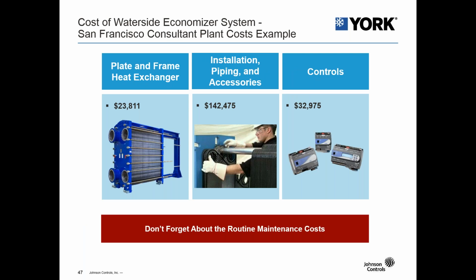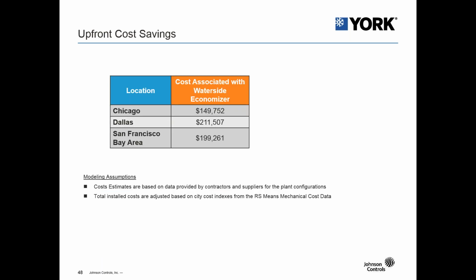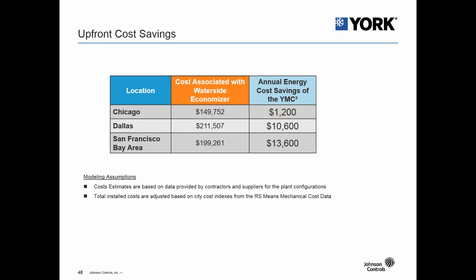But if we look at the first cost of a water side economizer system, once you take into account the first cost of the plate and frame heat exchanger, all the installation, piping and accessories, and the controls, and not even accounting for routine maintenance to maintain the water side economizer, doing yearly cleaning and ensuring that it's operating properly, those costs add up very, very quickly. So if we look at the upfront costs across the three locations, we see a range of $150,000 to over $200,000 just for a water side economizer system to be purchased and installed.